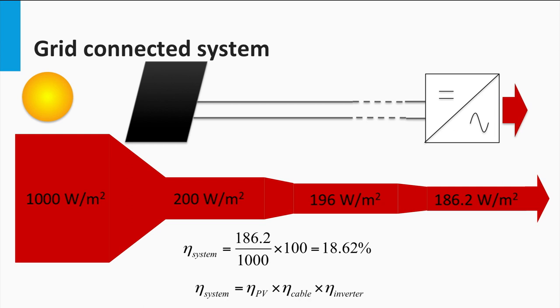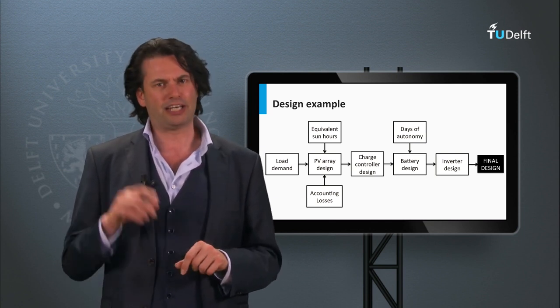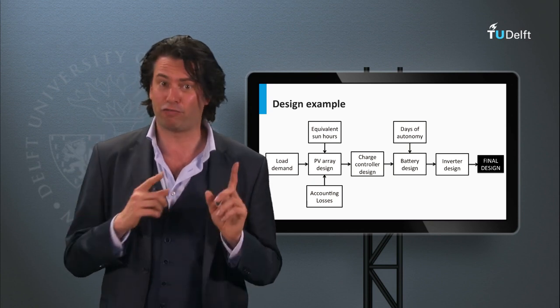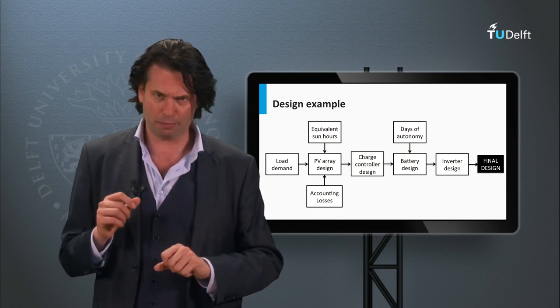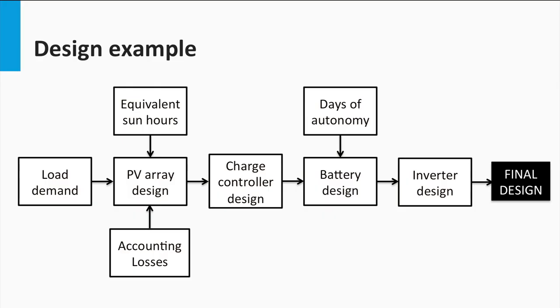It can also be said that the overall system efficiency is calculated as the product of the various component efficiencies. That is, eta system equals eta PV times eta cable times eta inverter. Now, let us move on to the design of a simple grid-connected PV system. As a quick recap, let us look back at the flowchart of the stand-alone PV system design process. You will remember that the system design process had several steps. Given that the grid-connected PV system topology is significantly different than that of the stand-alone PV system, how does the flowchart of the grid-connected PV system differ from the stand-alone system design?